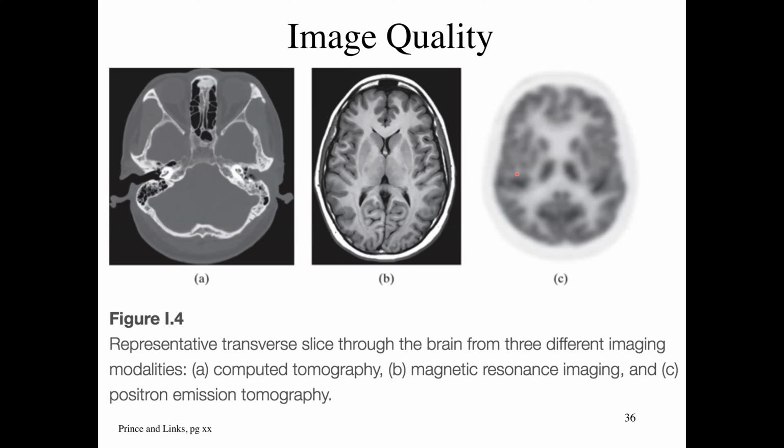The other thing is if you have, say, a pair of scissors or a wrench, and you walk into an MR scanner and you forgot you had the scissors in your pocket or the wrench in your hand, when you feel the magnetic field grab the thing and pull it, it's too late. You're not holding that thing, right? It's gone. And it's spectacular to watch it go, right? So that's the problem with MR. The main problem, that's how people have died at MR scanners, mostly.